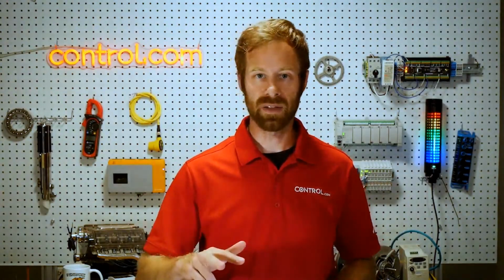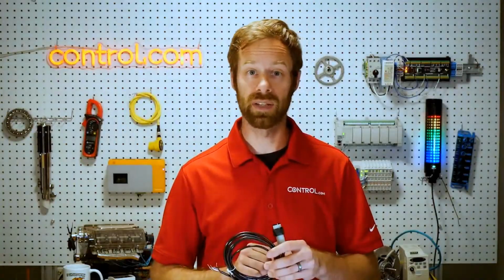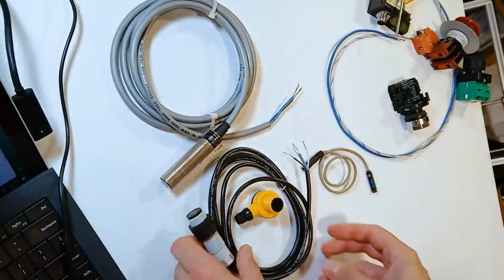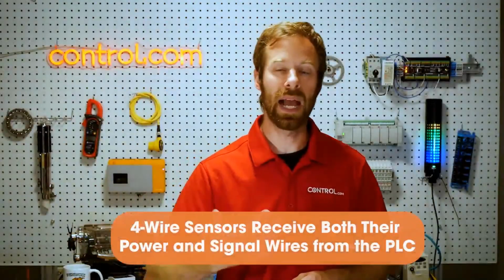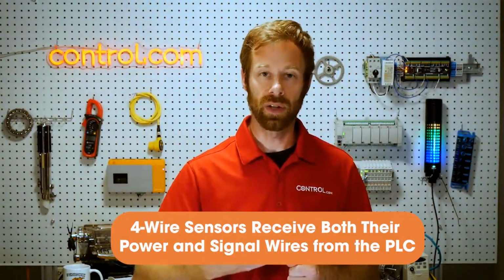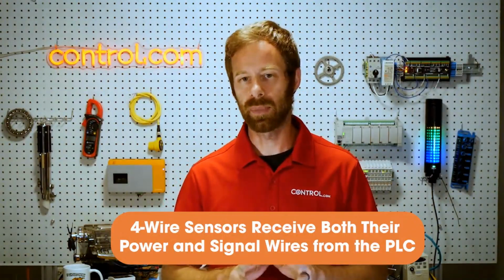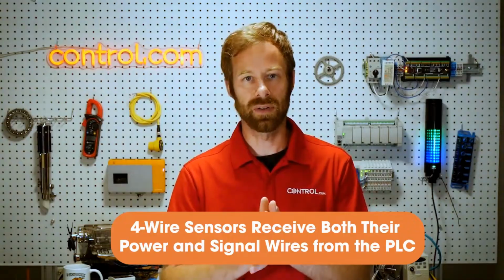goes. 3-wire sensors actually operate exactly like 3-wire digital sensors, the discrete ones. We have a plus and a minus to supply the internal working voltage for the sensor itself, and then the 3rd wire supplies the current or the voltage that we need. Finally, we have 4-wire sensors which receive both their power and their signal wires from the PLC. There's a couple of different ways that analog signals can travel.